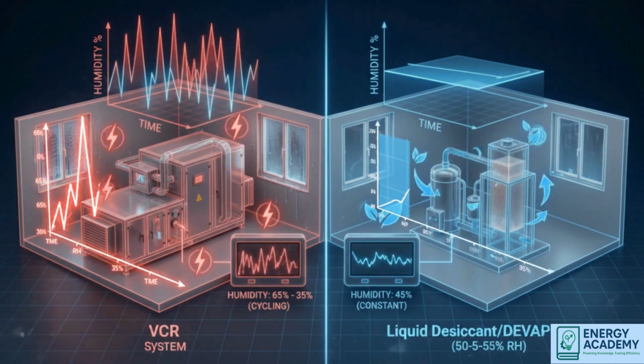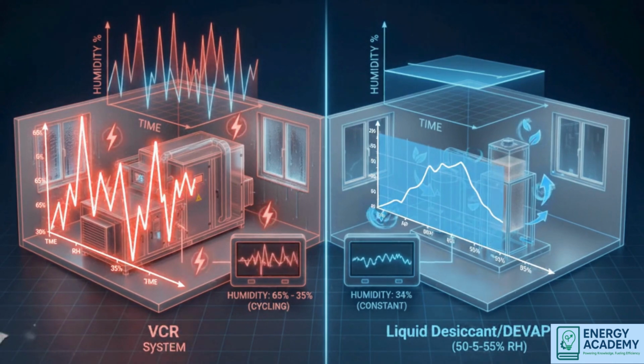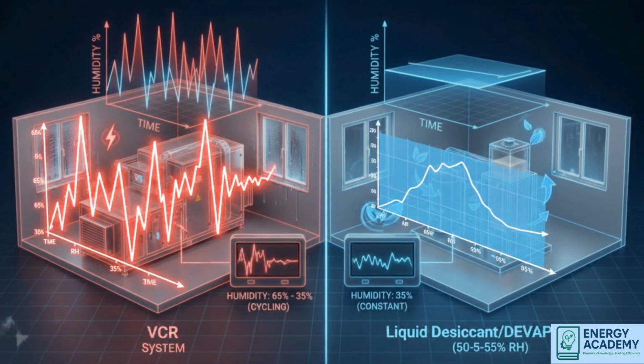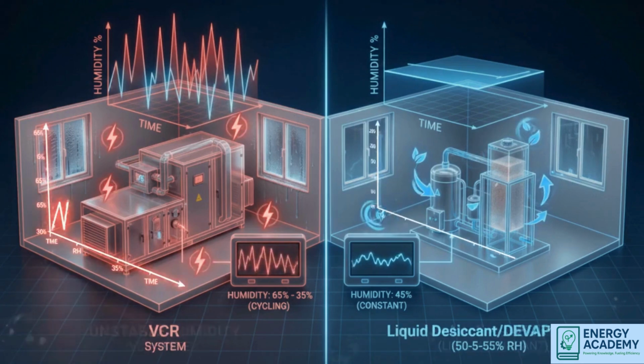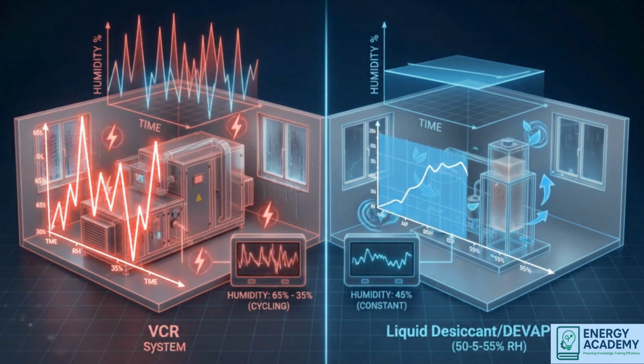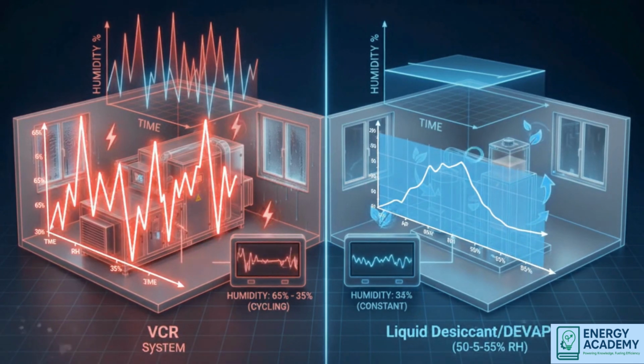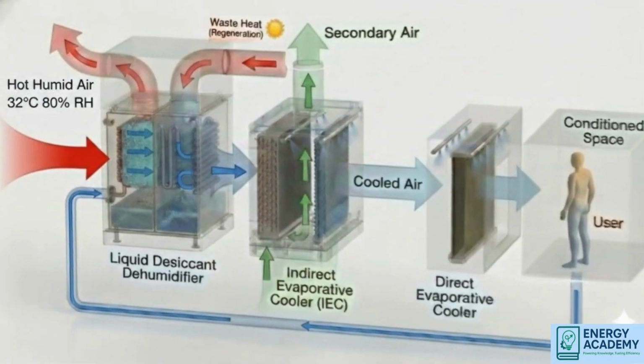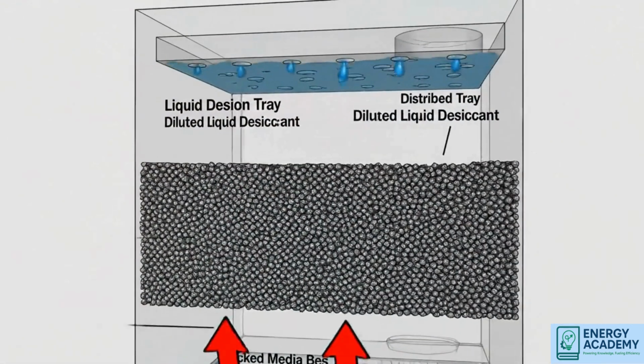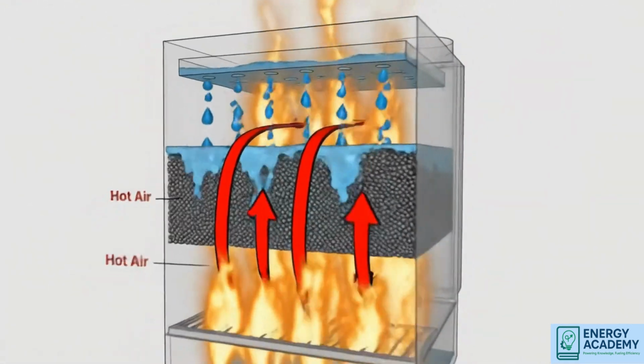Moreover, liquid desiccant DEVAP provides precise humidity control. Unlike conventional HVAC, humidity is controlled independently of temperature, critical for textile quality and worker comfort. Most importantly, liquid desiccant regeneration requires only low-grade heat.